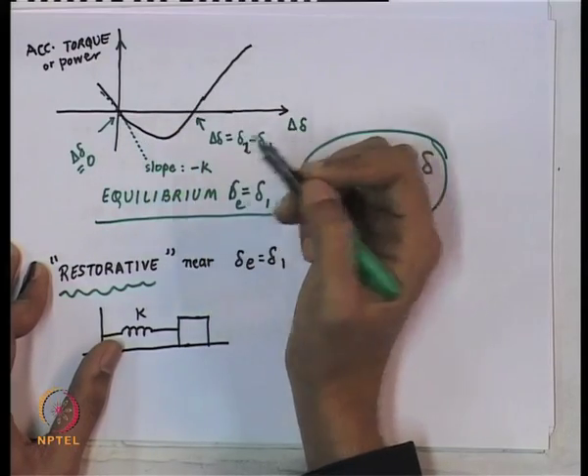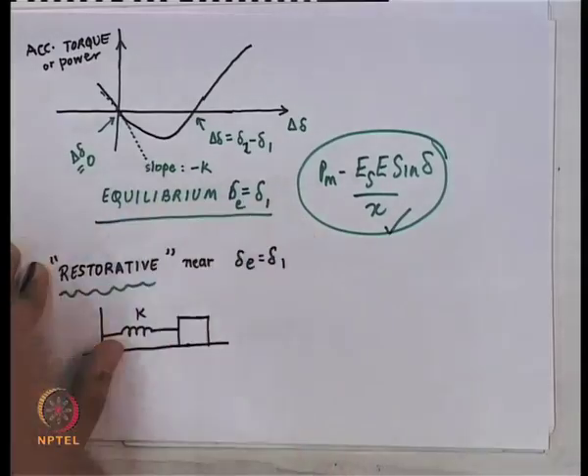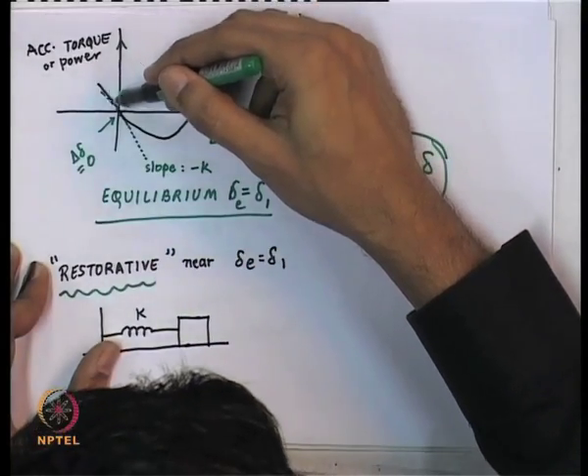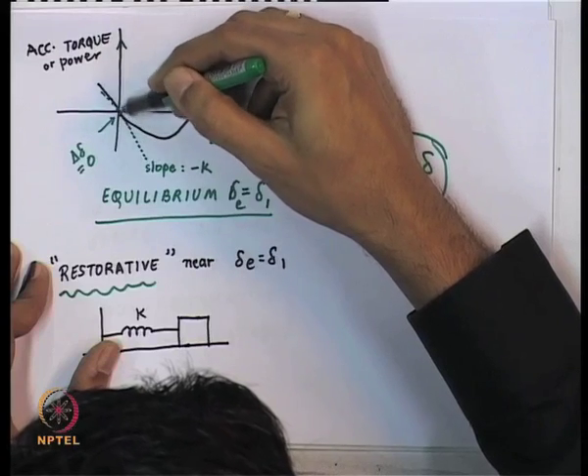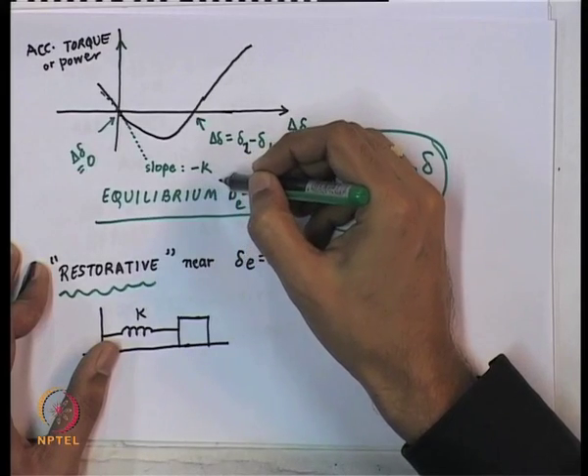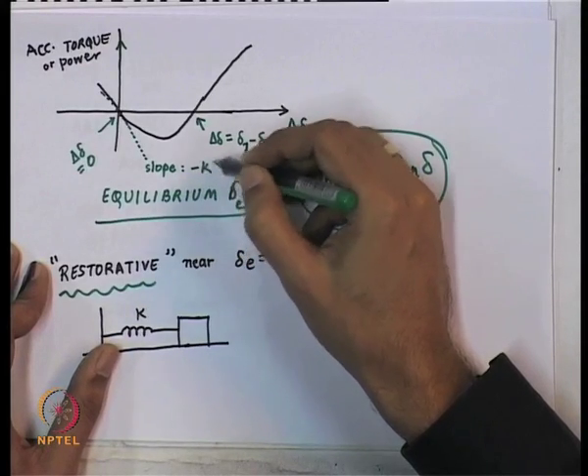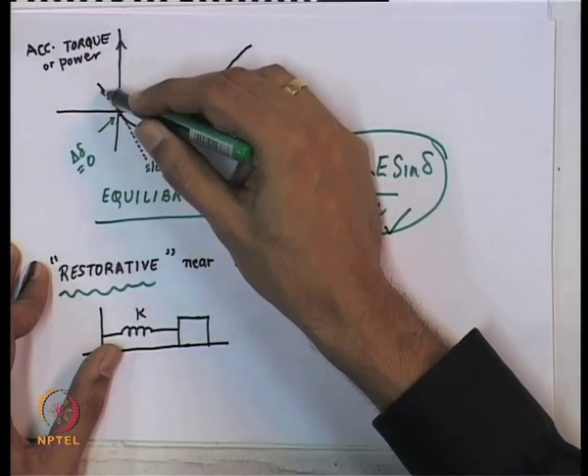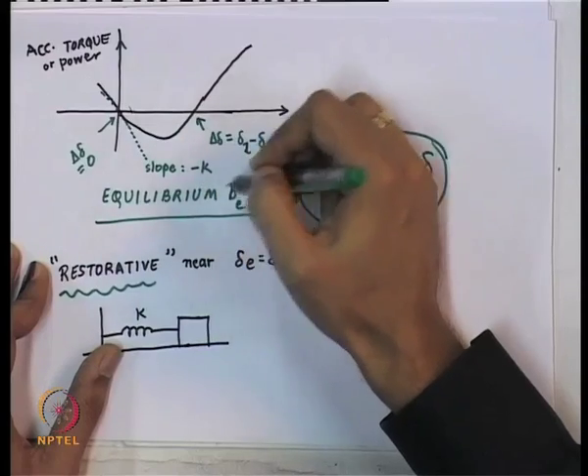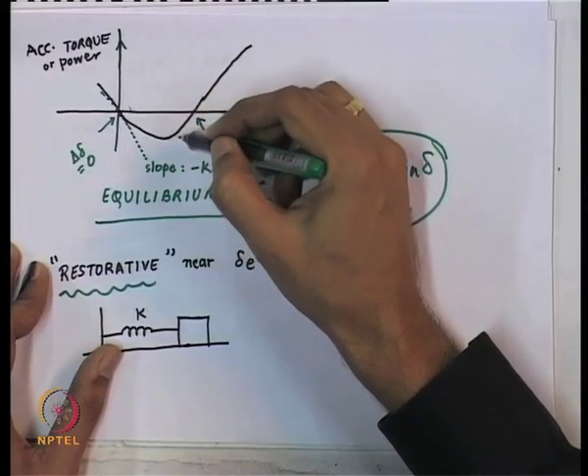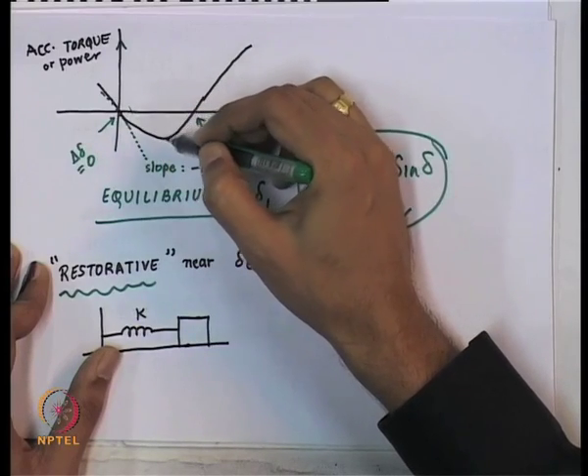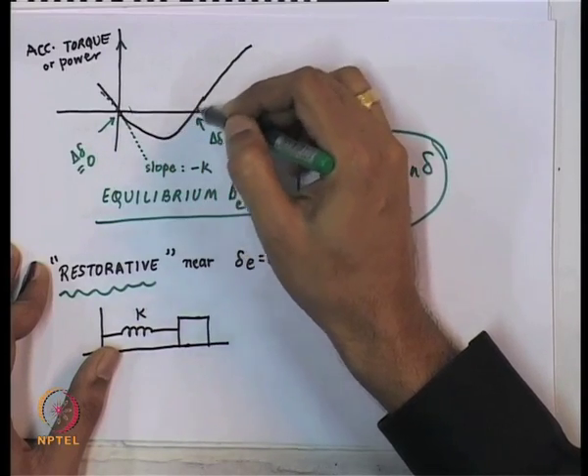So for small disturbances we can treat the torque as restorative, but for large disturbances it is not correct to assume it is always restorative. In fact, when we did the linearized analysis, what we effectively took was the slope of this particular curve at the equilibrium point. This slope was the k we talked about. For small disturbances, you can use the straight line with slope minus k, but for large disturbances the accelerating torque may not be restoring after some point.